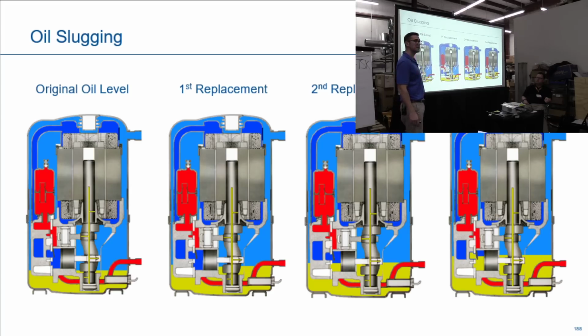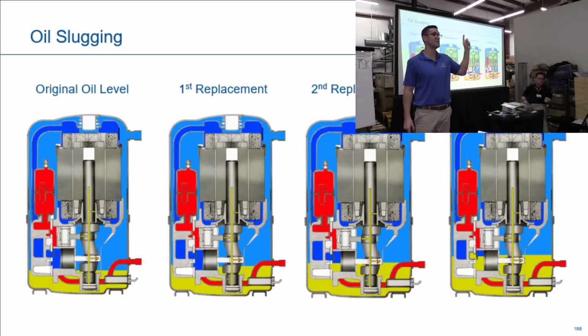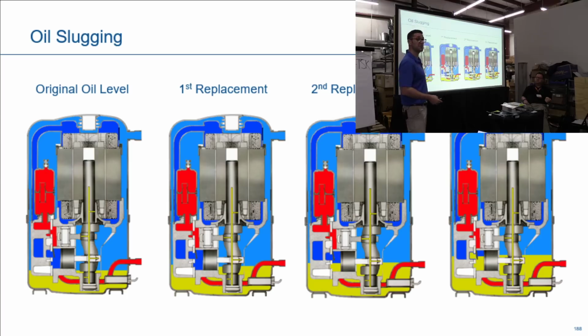And it fails. The first one probably fails on what? What is the first one you think fails on? No oil, which is what? What kind of failure? Seized compressor. Thank you. So the compressor seized. But you didn't get this one inspected, so you don't know. The guy didn't pour the oil out. Because if we would have dumped it out and it was supposed to be 10 or 20 ounces and there was 1 ounce in there, where's that oil now? It's somewhere in that system. Right? Does that make sense?